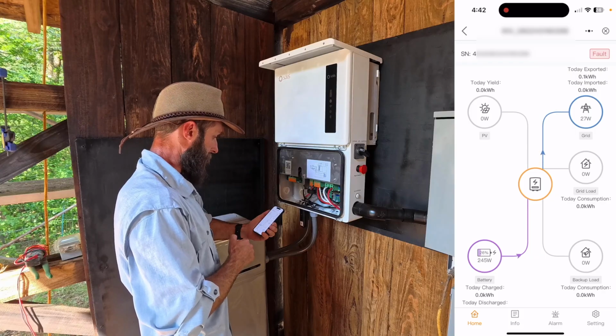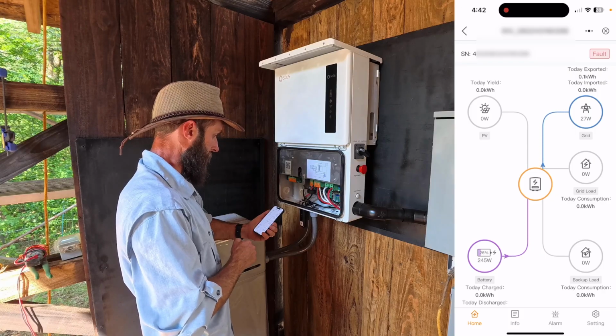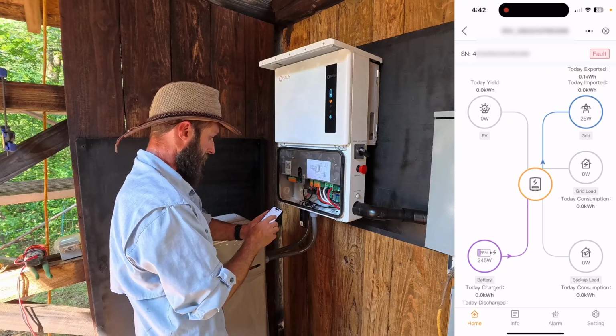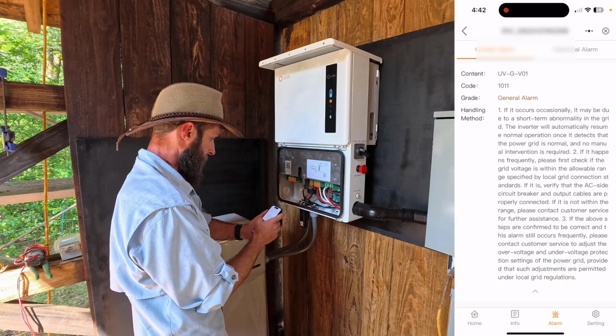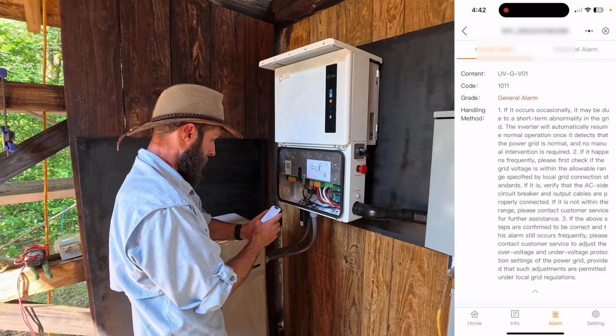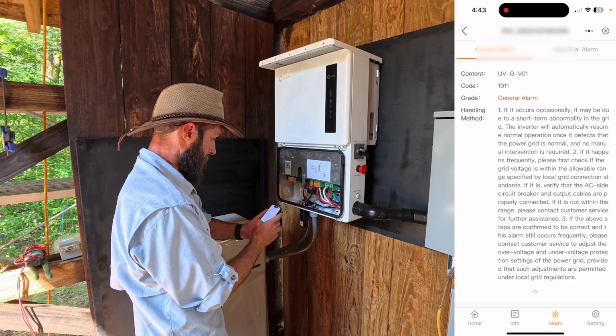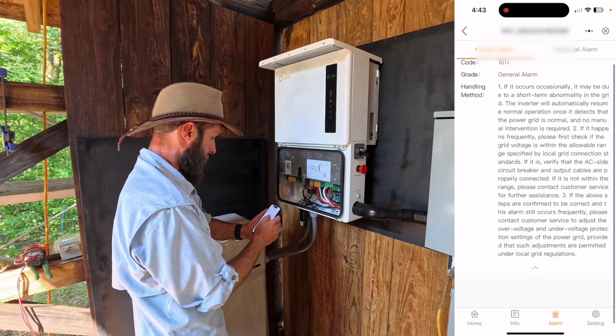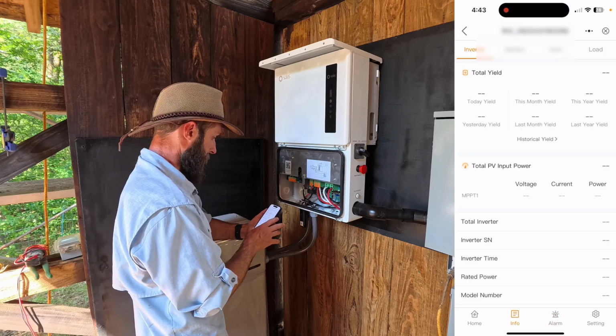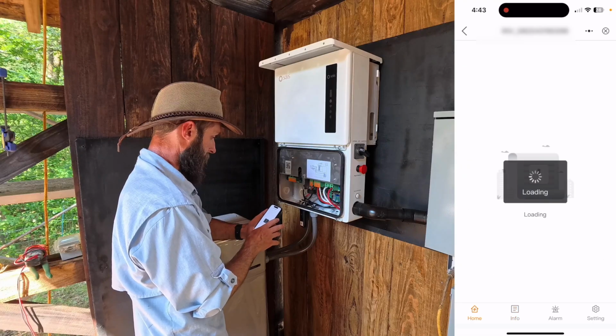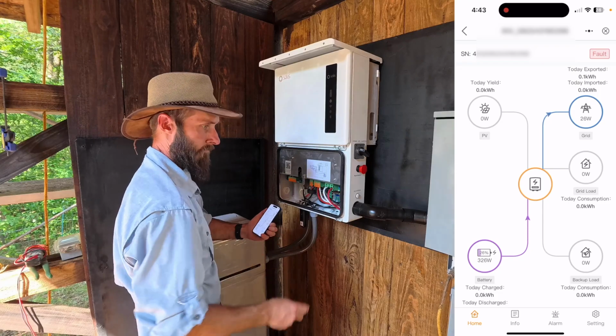Alright, I don't like that it's showing 27 watts going to the grid. It's got a fault. This fault, UVGV01, is an under voltage fault—essentially it's low voltage. You can't find it documented anywhere, and when I called tech support, they didn't really even know what this was. The general sense we got was that it's low voltage coming from my grid. Since it travels such a long way, there's a little voltage drop, and it didn't like it. It doesn't show up all the time, but occasionally.